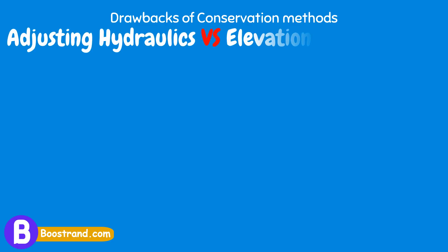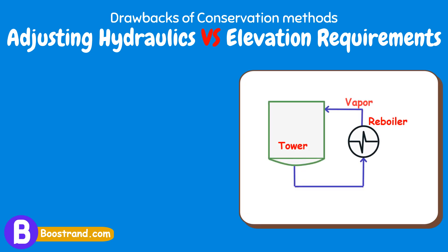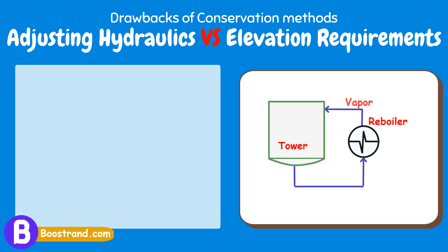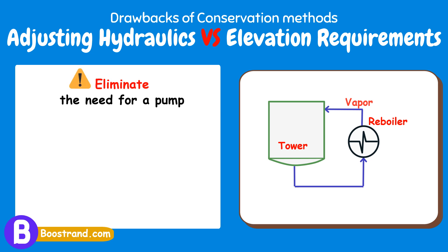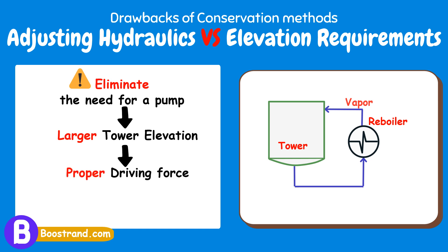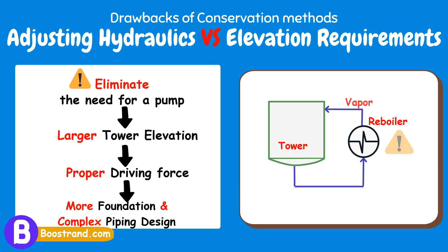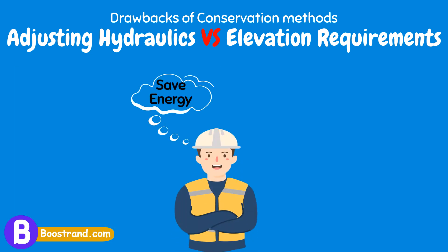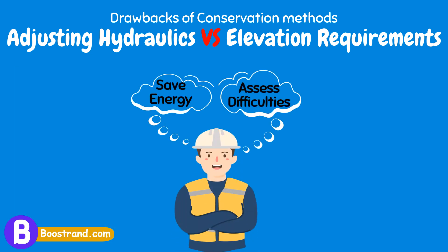Another example of engineering difficulties engineers may face is when using once-through reboilers in a tower configuration. As highlighted before, this shall eliminate the need for a pump, which is great. However, this shall also lead to a larger tower elevation to ensure proper driving force. This means more foundations and complex piping design, and in some cases it may be difficult to achieve the required design that provides proper recirculation from the tower to the reboiler and back. So as we are putting energy savings in mind, we should assess the difficulties we shall face and ensure they are well addressed.